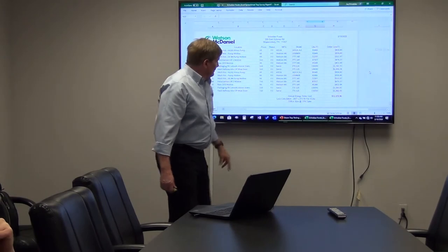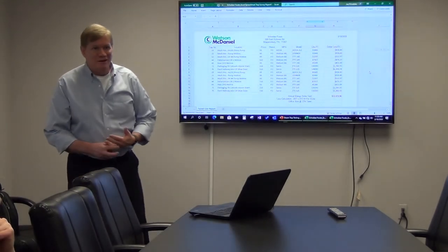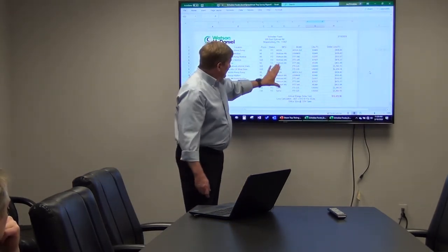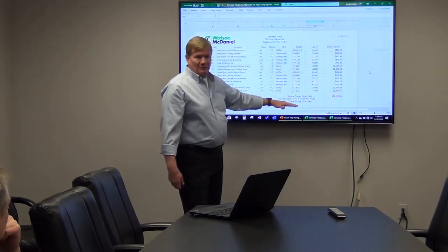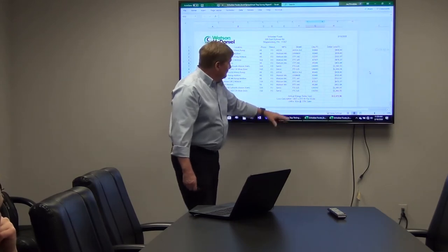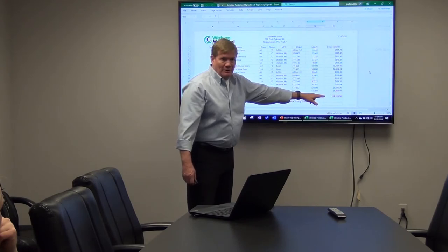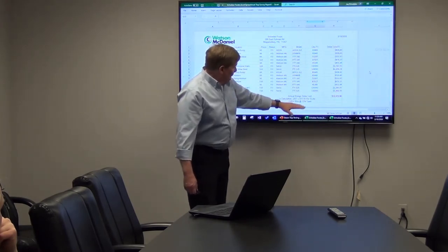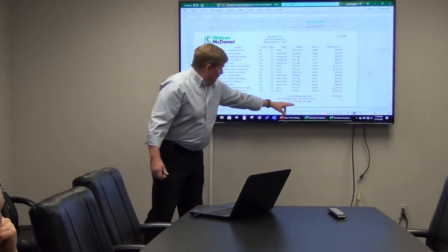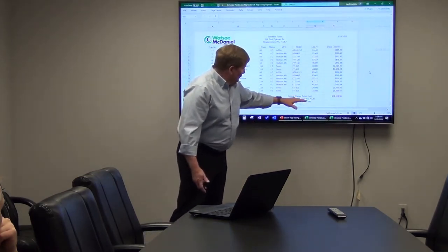You can see across the board, you say, wow, $12,000, that's a lot of money. Well, I always put this in here. This Access database is based on if these traps are in operation 365 days a year, 24 hours a day. So what the software company does is we'll say, okay, that's going to be a very high number. And the default value, as far as we're going to say these traps don't fail 100% wide open, the default value is only 33%.